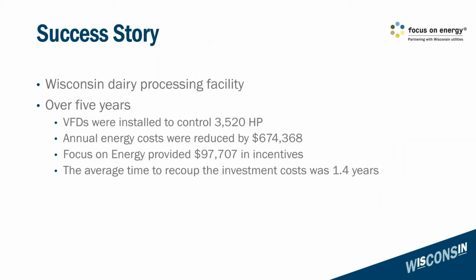There is a Wisconsin dairy processing facility that over the last 5 years has done a variety of VFD projects. Over those 5 years, they are controlling a total of 3,520 horsepower. This was a new construction situation, and they had controls and efficiency in mind as they were progressing through creating the facility. They're putting VFDs on process pumps, process fans, HVAC pumps—anywhere it was going to be beneficial—and they knew they were going to save energy and create a better situation for themselves.